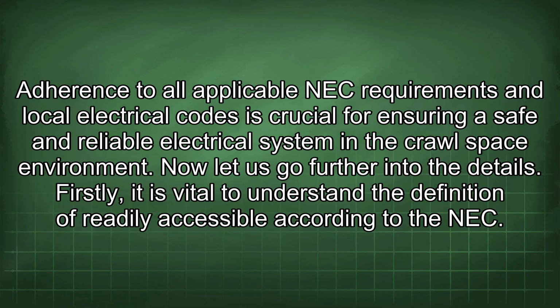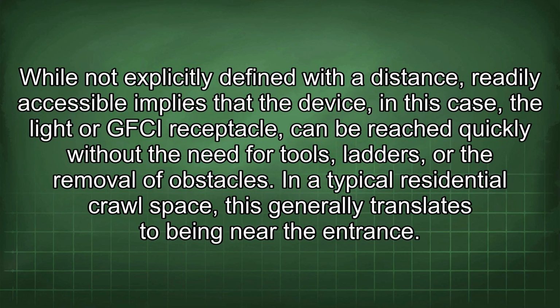Firstly, it is vital to understand the definition of readily accessible according to the NEC. While not explicitly defined with a distance, readily accessible implies that the device, in this case the light or GFCI receptacle, can be reached quickly without the need for tools, ladders, or the removal of obstacles. In a typical residential crawl space, this generally translates to being near the entrance.